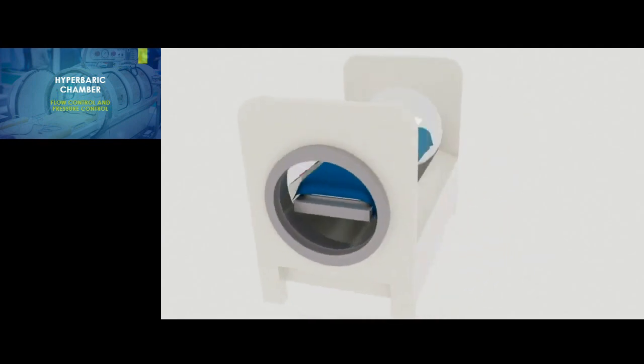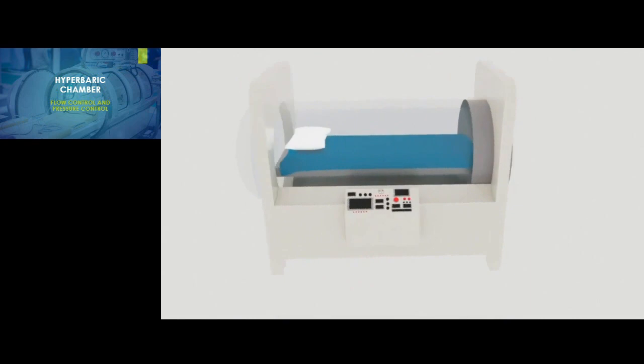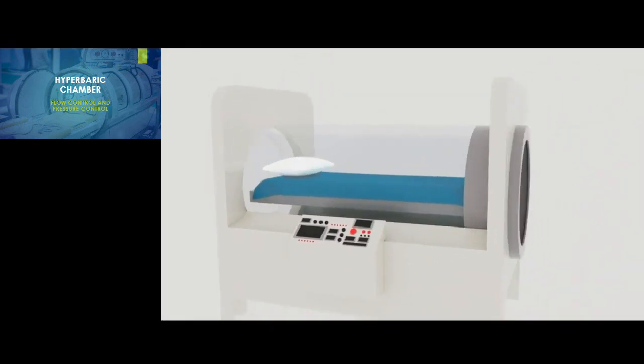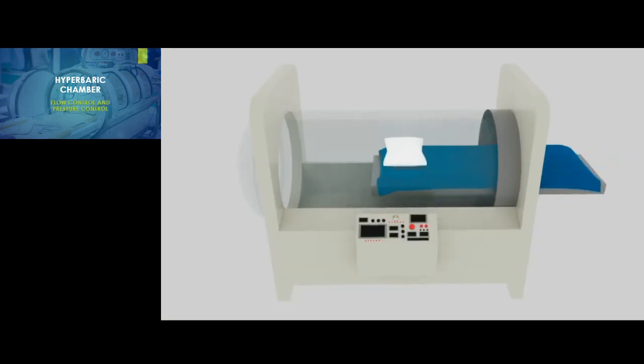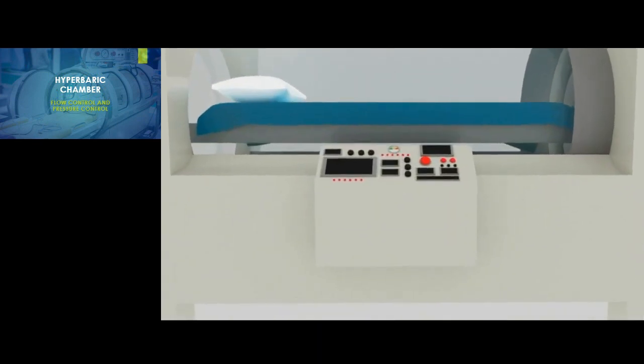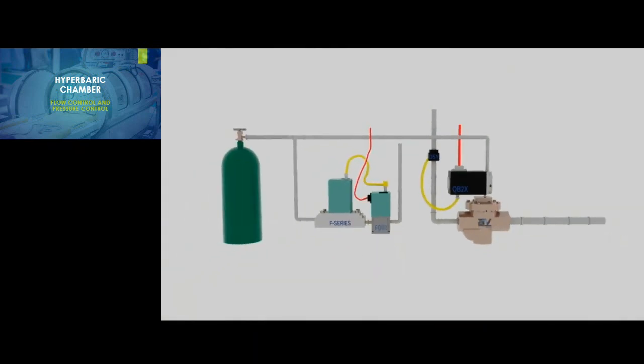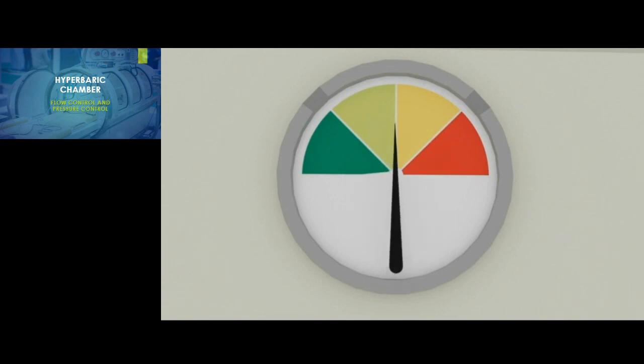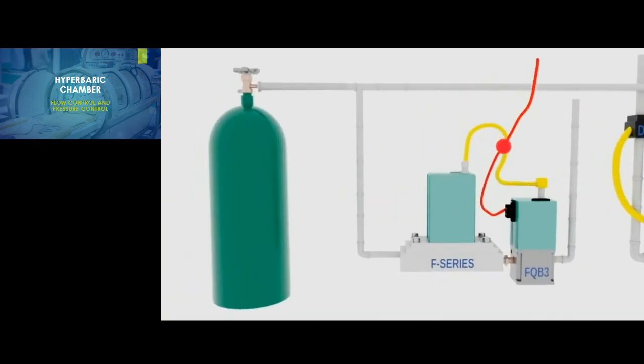A hyperbaric chamber is used for oxygen therapy. This aids in the treatment of decompression sickness in divers, traumatic brain injuries, and the healing of wounds. A flow controller and a back pressure regulator maintain the environment. To pressurize the chamber, an electronic signal is sent to the flow controller and the electro-pneumatic back pressure regulator assembly. The flow controller allows oxygen to enter the chamber at a specified rate. The F-series flow monitor measures the flow rate and provides feedback to the FQB3. The FQB3 will then adjust as needed to maintain the specified flow rate.